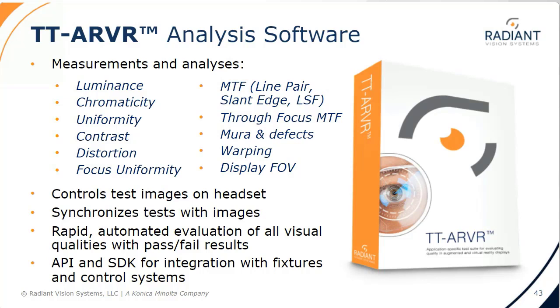Using custom tolerances, the software can also output pass-fail results. Because TT-ARVR is meant as an automated visual inspection platform, the software also offers a built-in API and SDK for integration into automation fixtures and control systems.